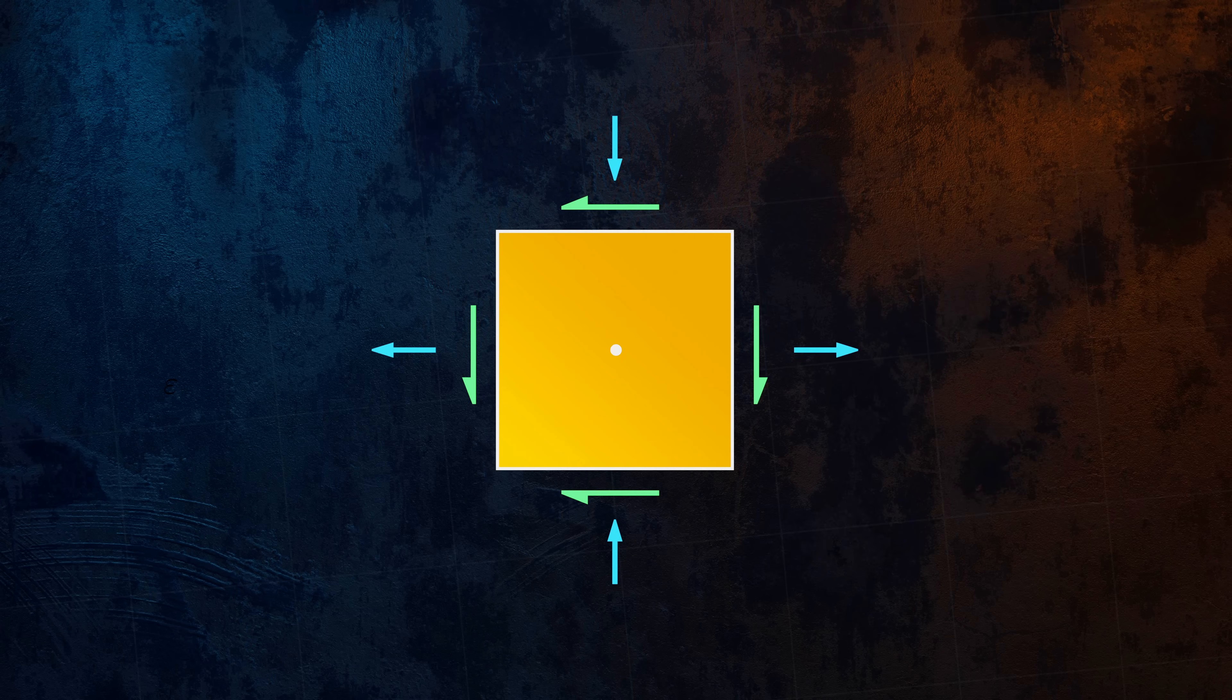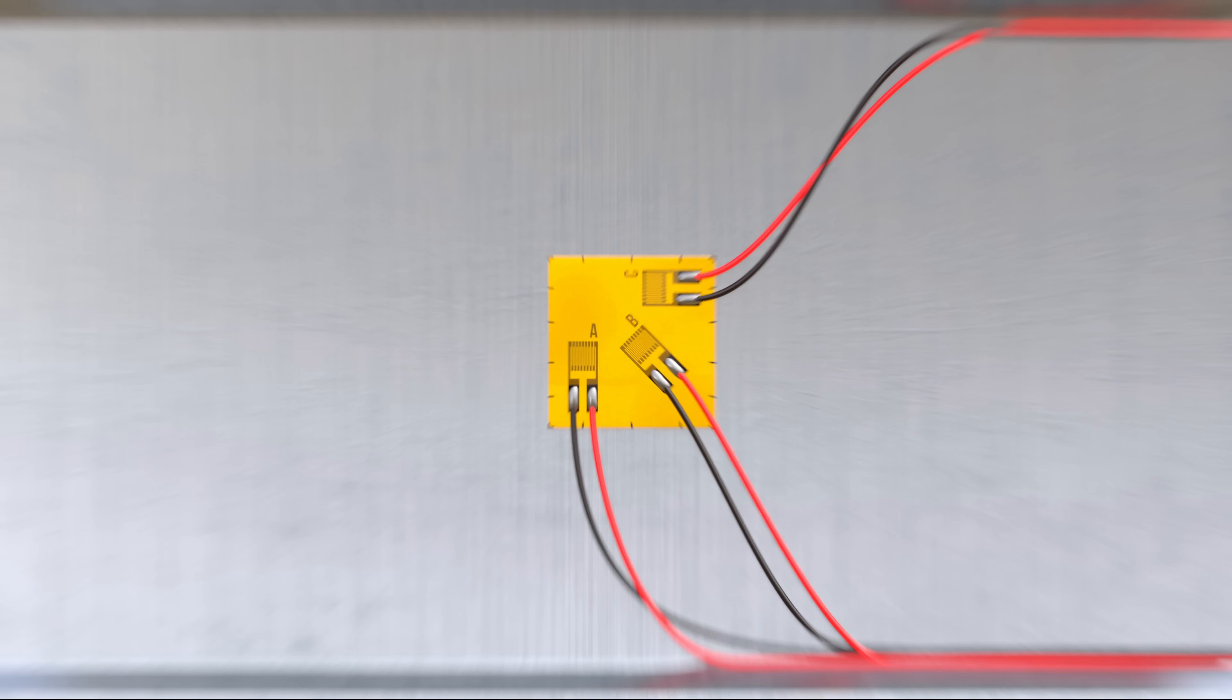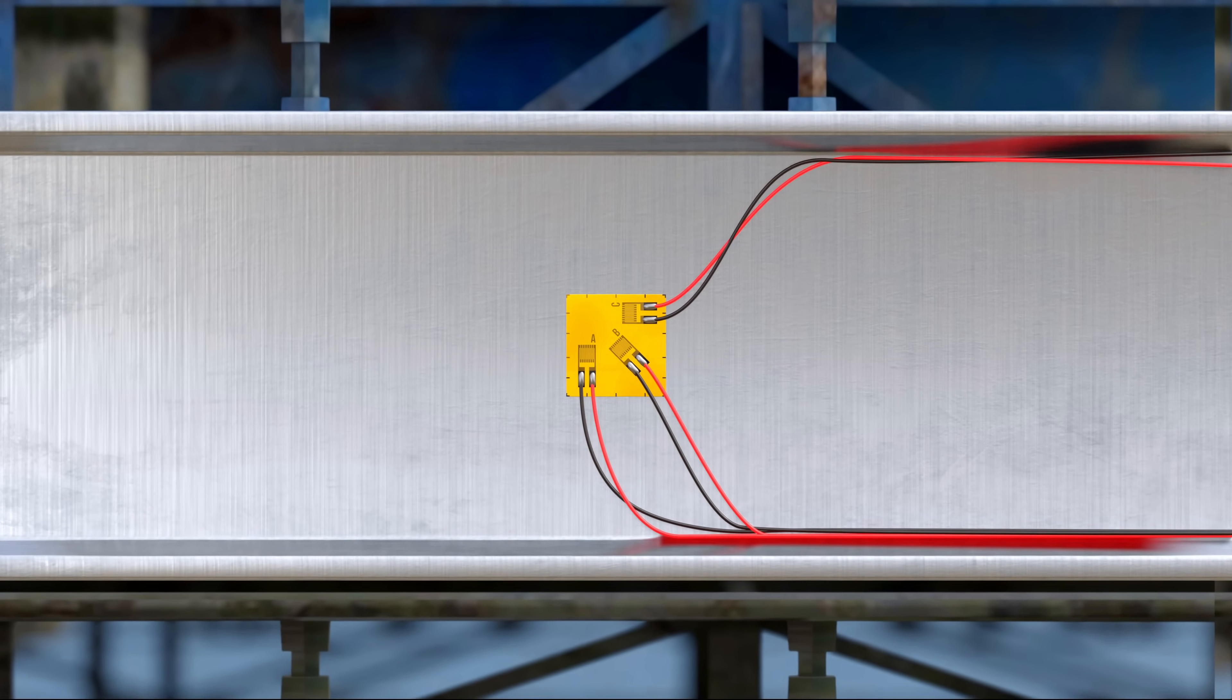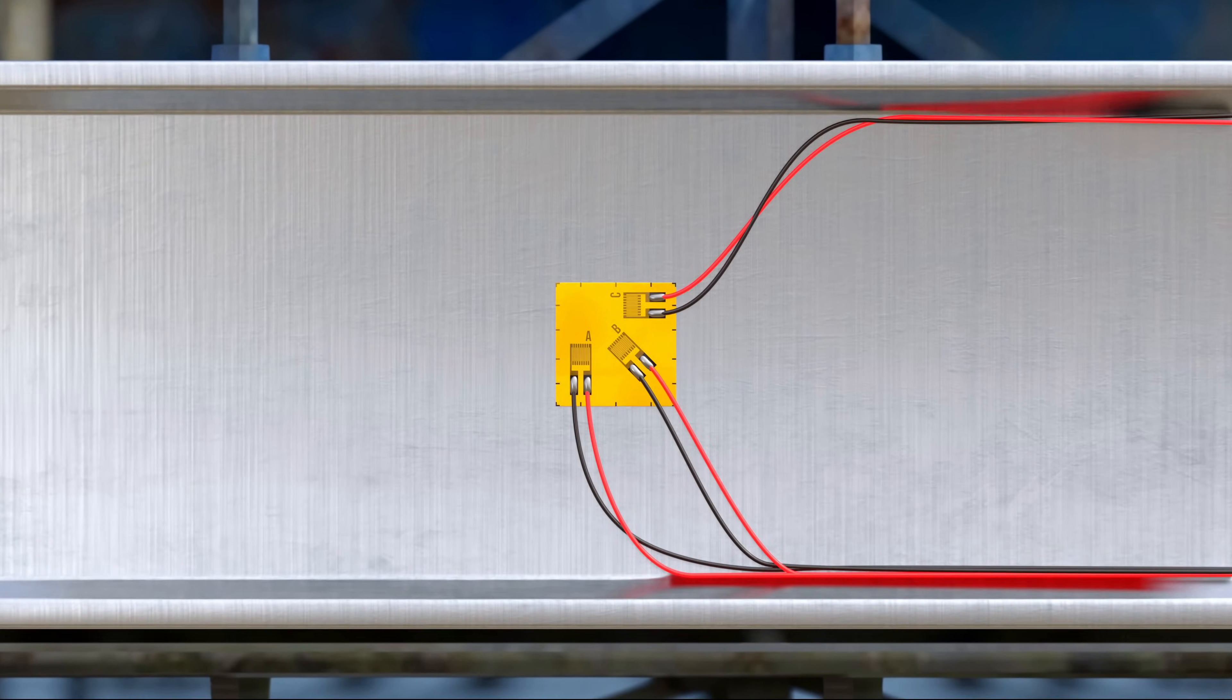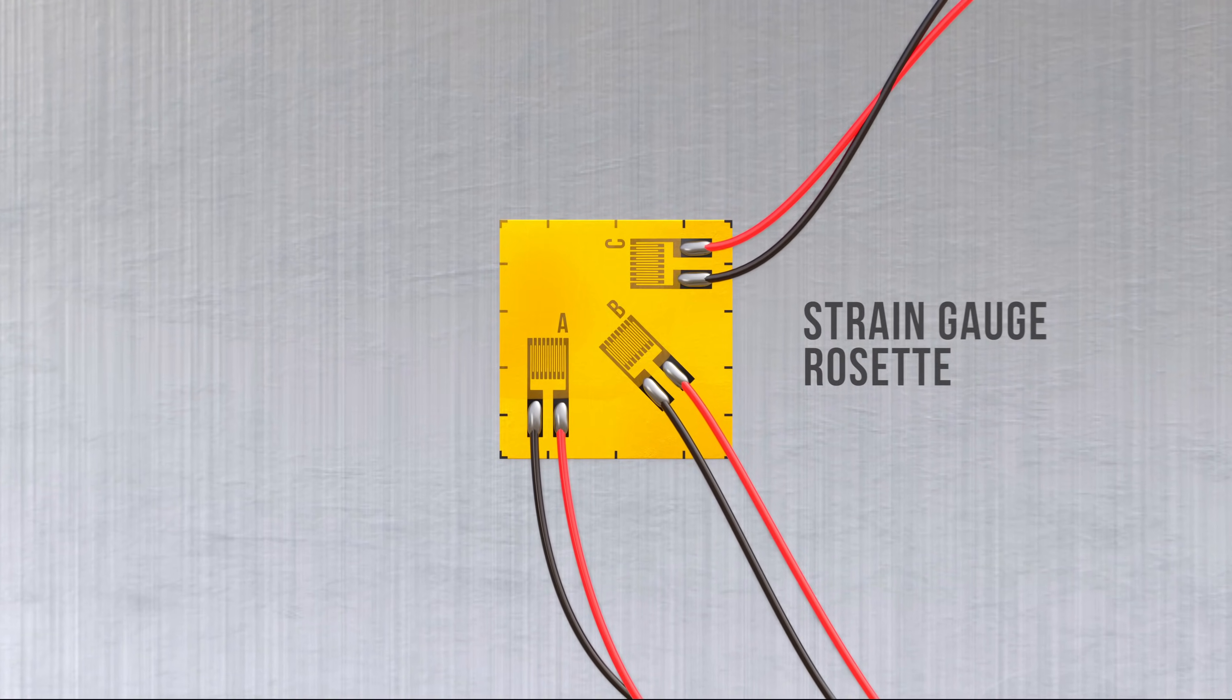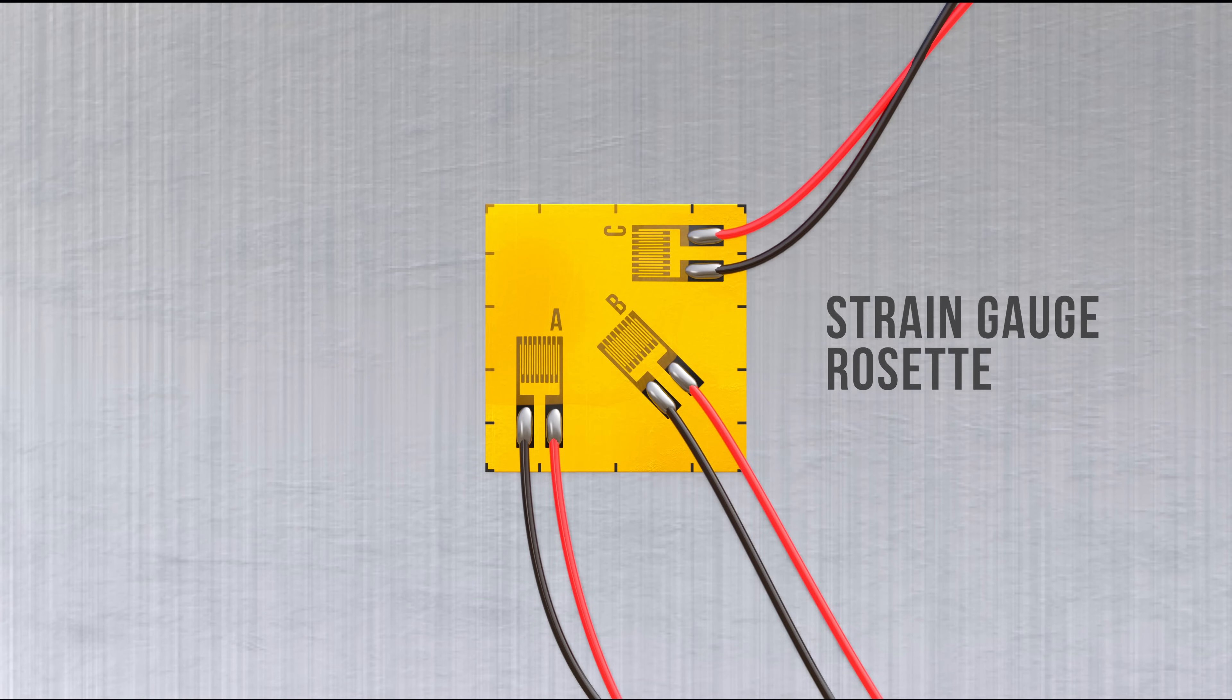For this reason, strain gauges are often used in sets of three, separated by angles of 45 or 60 degrees. This arrangement is called a strain gauge rosette. The rosette provides the normal strain at three different angles, which is enough information to fully define the strain state at a single point.